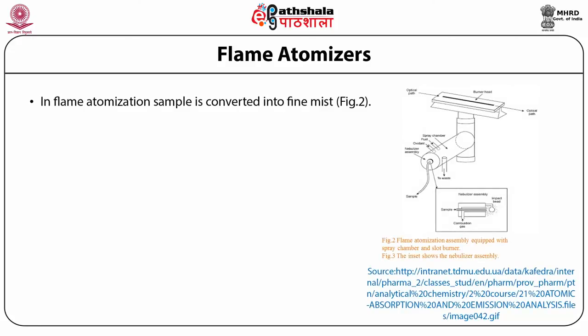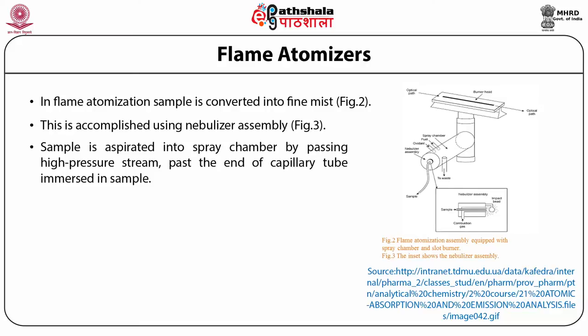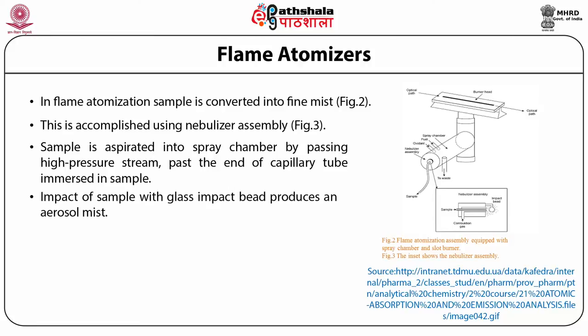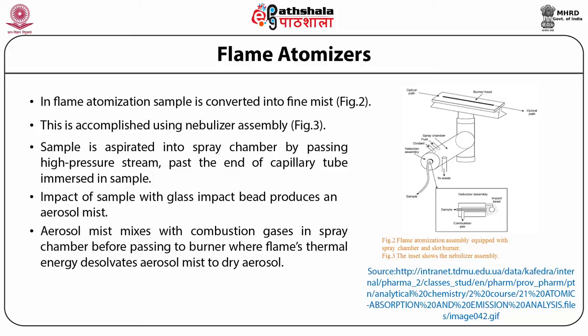In flame atomization, the sample is first converted into a fine mist consisting of small droplets of solution, as shown in figure 1. This is accomplished using a nebulizer assembly shown in figure 2. The sample is aspirated into a spray chamber by passing a high-pressure stream of combustion gases past the end of a capillary tube immersed in the sample. The impact of the sample with the glass impact bead produces an aerosol mist. The aerosol mixes with combustion gases in the spray chamber before passing to the burner, where the flame thermally desolvates the aerosol mist to a dry aerosol of small solid particles.